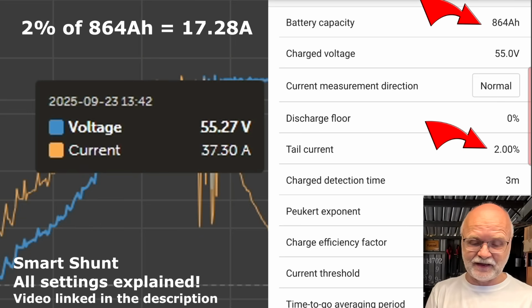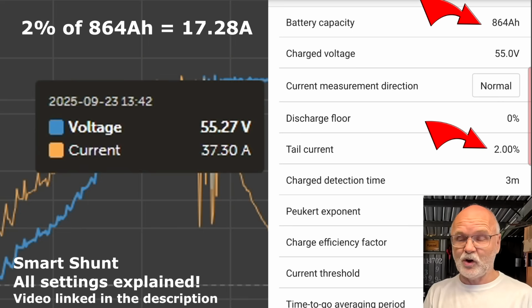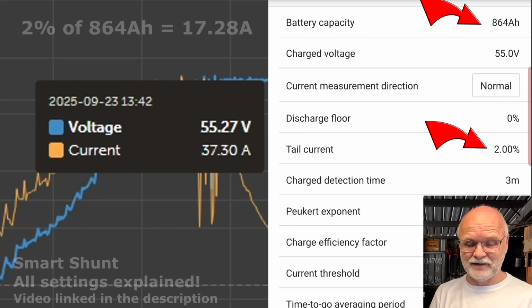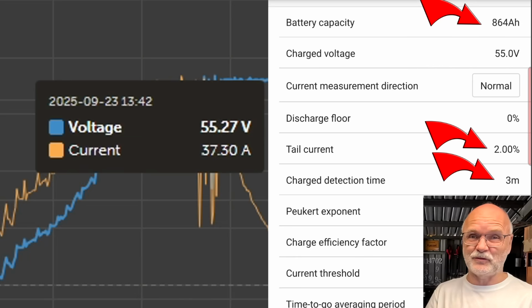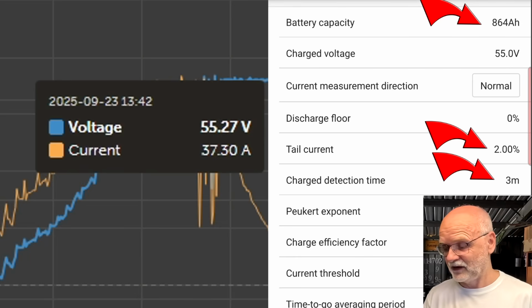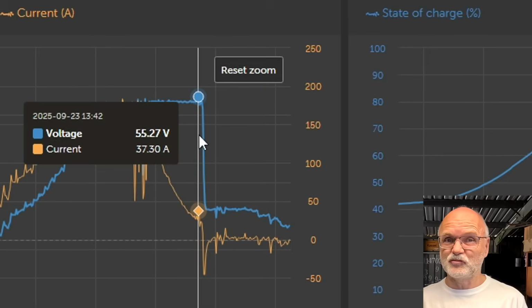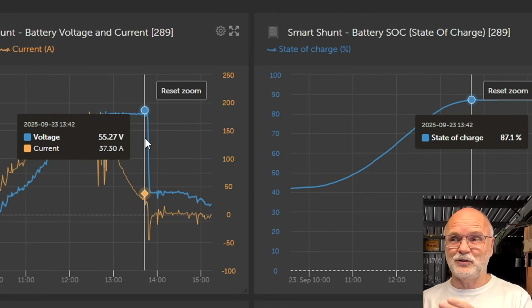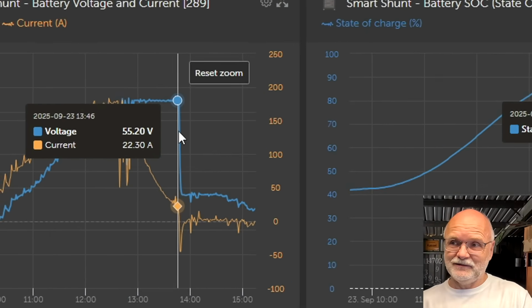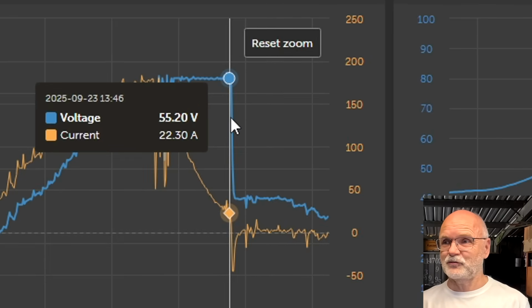And the charging detection time was 3 minutes. Obviously the current was still too high after 1 hour. The batteries were still absorbing, and we didn't meet these 3 criteria of the Smart Shunt to reset. So it didn't reset. It would have been wrong to reset to 100% because at this point the batteries were not at 100%. After 1 hour the MPPTs throttled down.